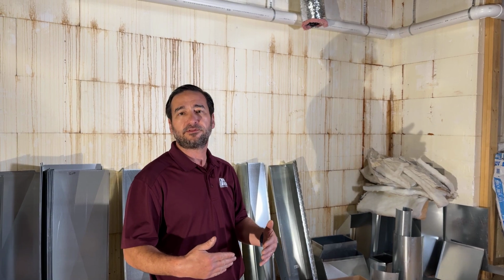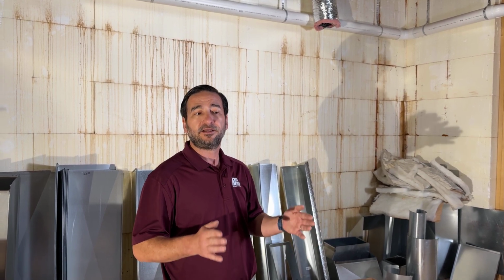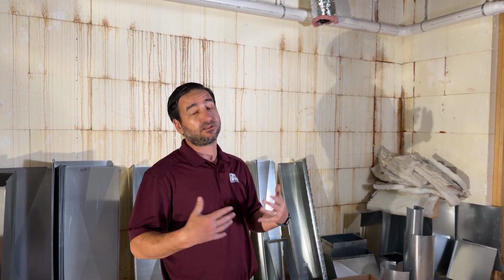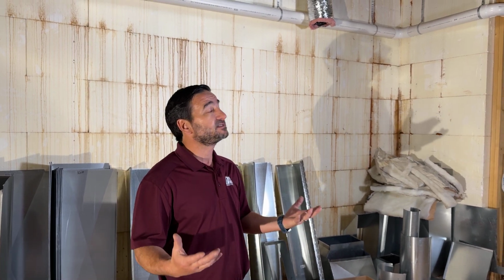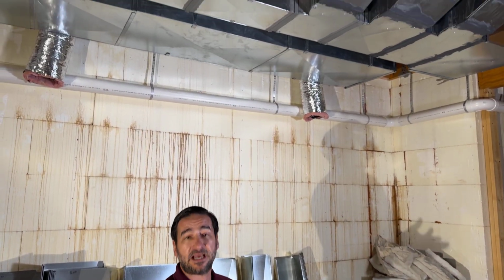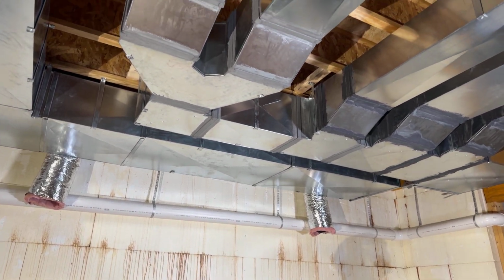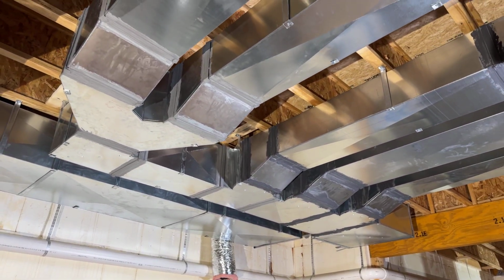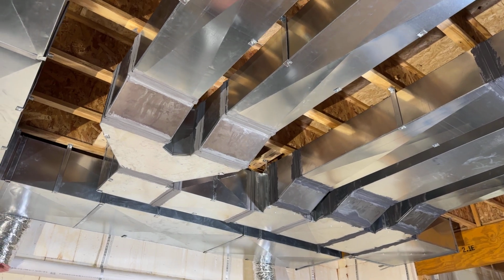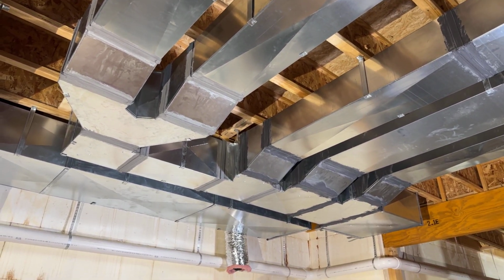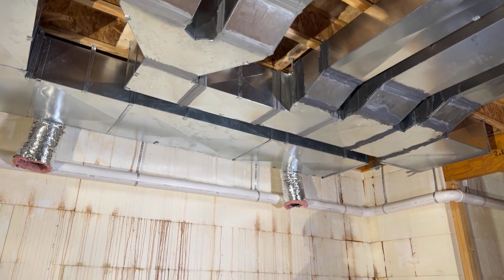So you have to find out what is the lowest airflow that the unit you're using will run on, and then you try to size your trunk duct to be able to accommodate that low airflow. So that differs in a normal HVAC system, because in that case you just have a lot less duct. But you can see from this system that there's obviously added cost involved with this, because there's a lot more material, there's a lot more labor, but the value is long term: you have less equipment to maintain, less equipment to replace, and it's a more elegant way to push energy around.